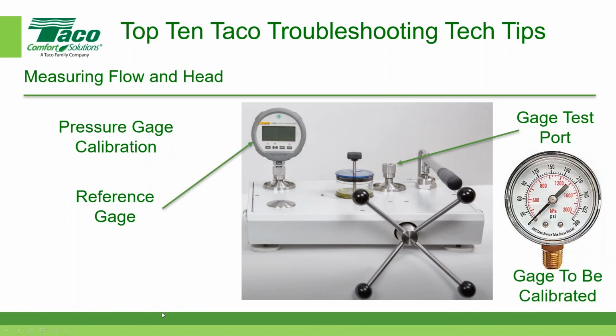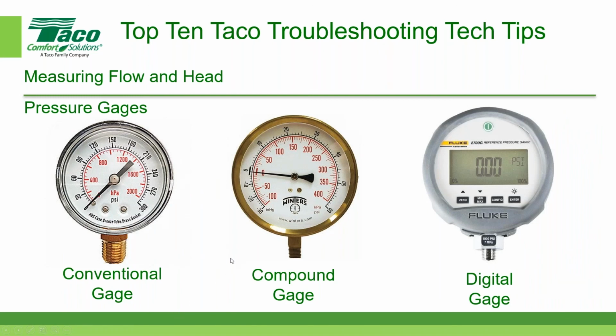Oh, and by the way, let me just go back here. The other thing is that when it comes to gauges, since we use them quite a bit for information, you want to pick a gauge where the mid-range of the gauge is fairly close to the reading that you're looking for. So for example, in this one on the left, the black lettering on the outside is PSI. Let's say that the actual pressure they were trying to read was 30 PSI. Well, in this particular case, you'd want that 30 PSI to be mid-range in this area over here. So the gauge might go from 0 to 60, and mid-range would be 30.